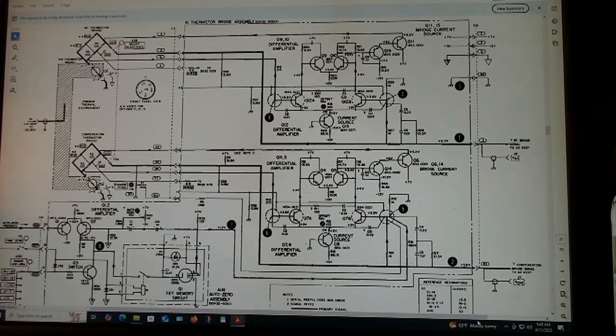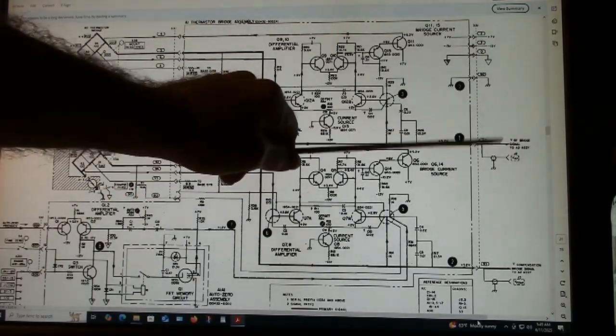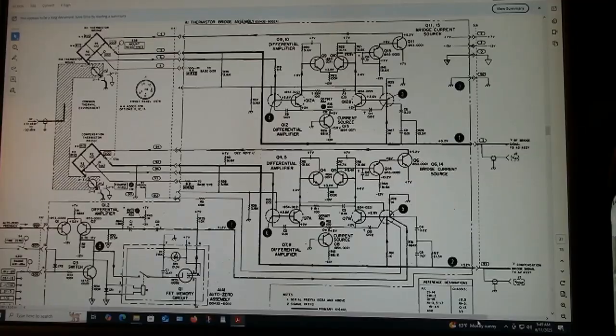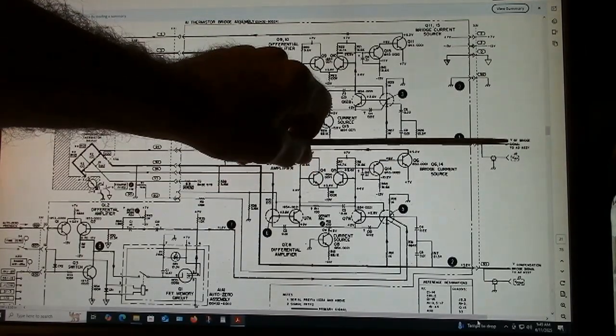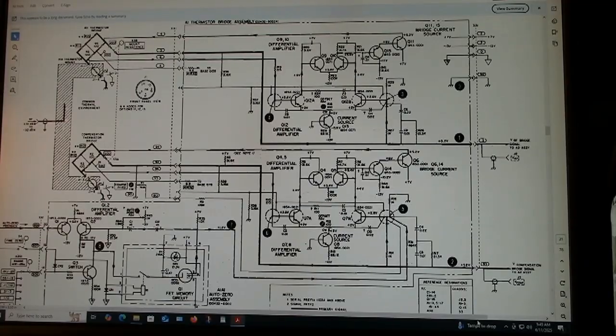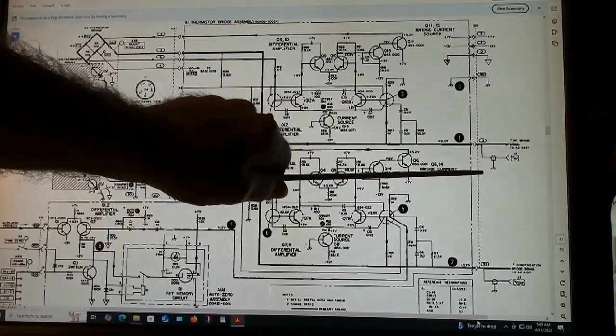So now with the bridge balanced, initially before applying RF power, you've got two outputs from this assembly. You've got the VRF output signal here and the V compensation signal here, and they'll be equal. When you apply RF here, it will start heating up this thermistor. That'll unbalance the bridge, and since that's going to change the biasing into that bridge circuit, that output voltage is going to vary. So now VRF, the output signal here, is going to vary with the amount of RF coming in.